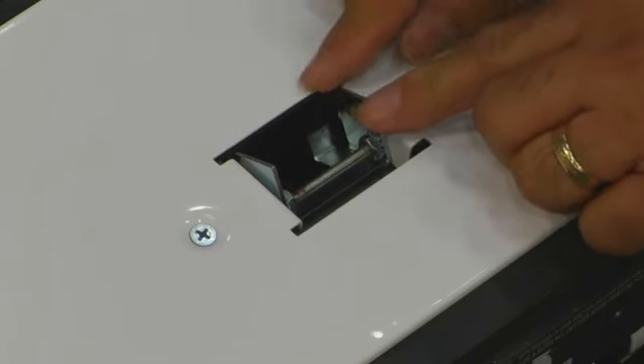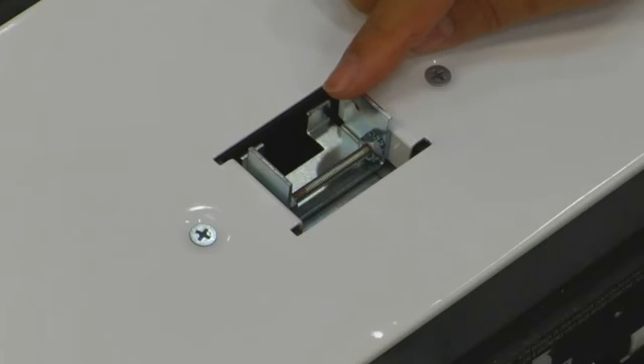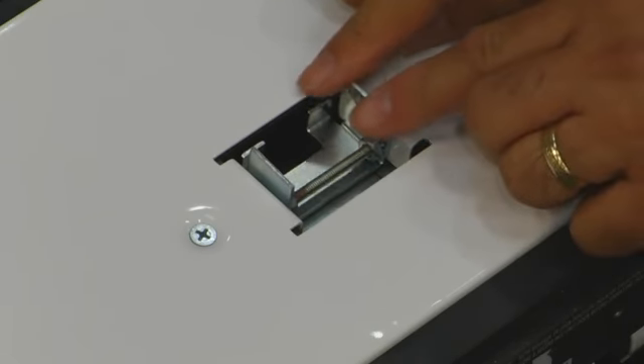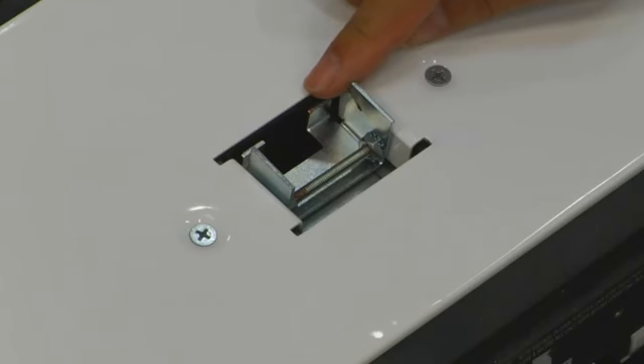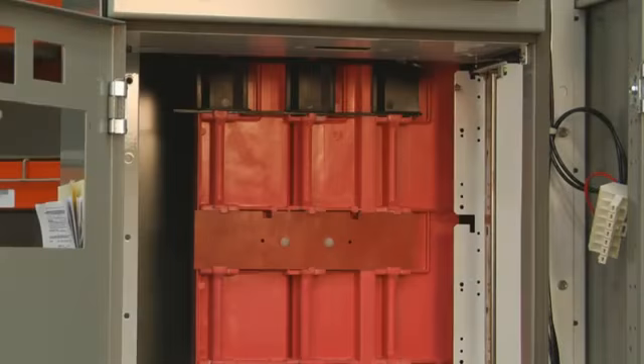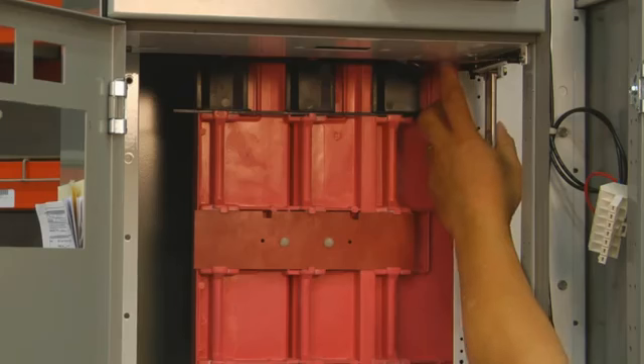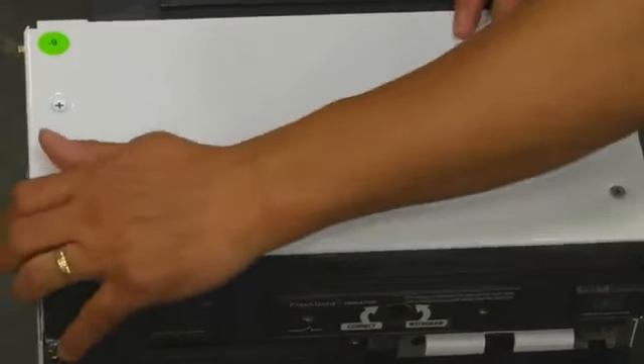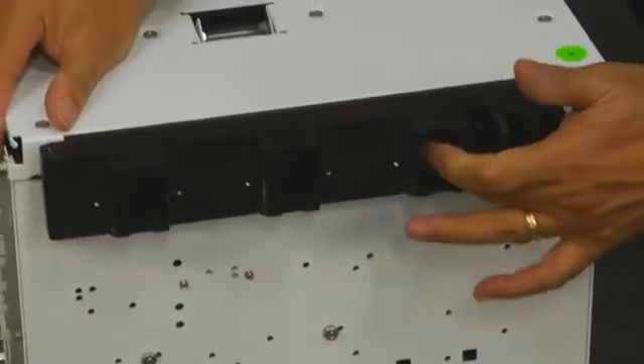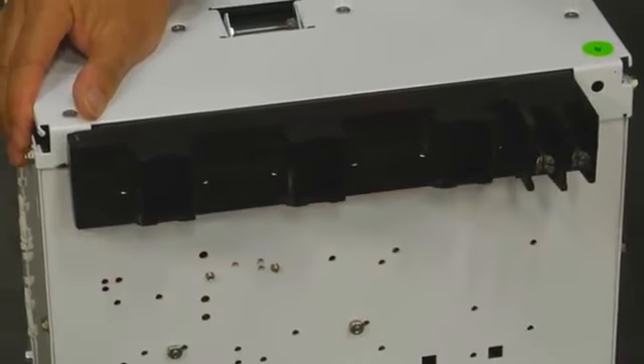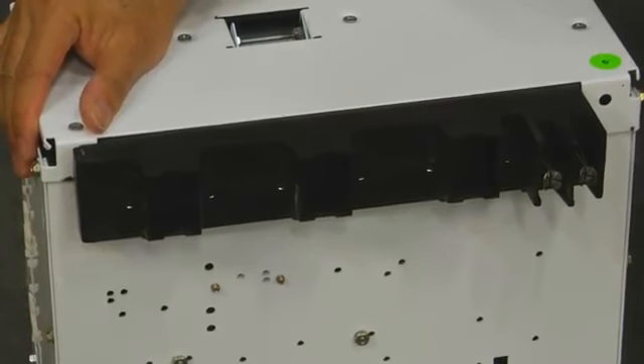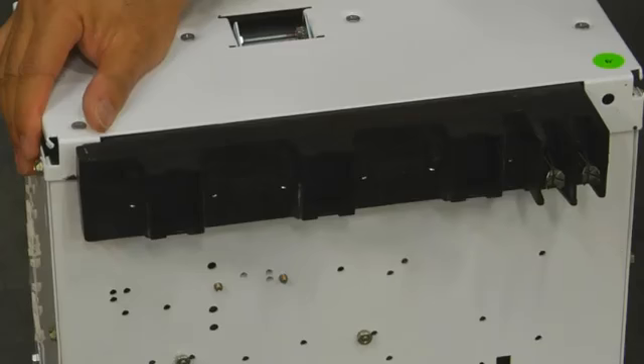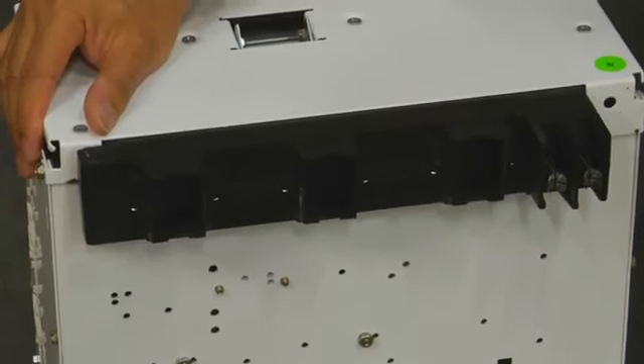Also, you can see that we have an active interlock system on our FlashGard unit that prevents the user from extracting the unit from the cabinet whenever the stabs are engaged on the vertical bus, or from reinserting the unit back into the cabinet if the stabs are inadvertently left extended. But in addition, there are two independent shutter mechanisms. One of them can be found inside the MCC cabinet, and it automatically closes whenever a FlashGard unit is removed from the cabinet. The other can be found on the FlashGard unit itself. This shutter closes whenever the stabs are retracted into the unit. Together, these shutter mechanisms automatically isolate both the vertical bus and the power stabs whenever FlashGard units are inserted or removed from the MCC cabinet.